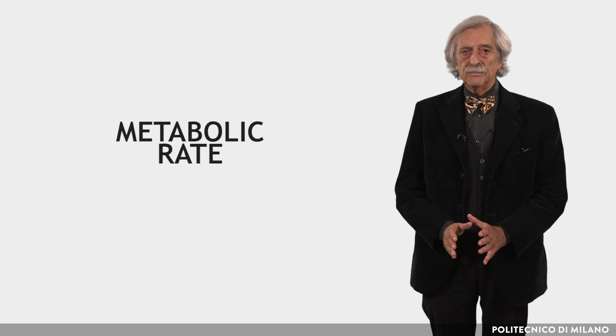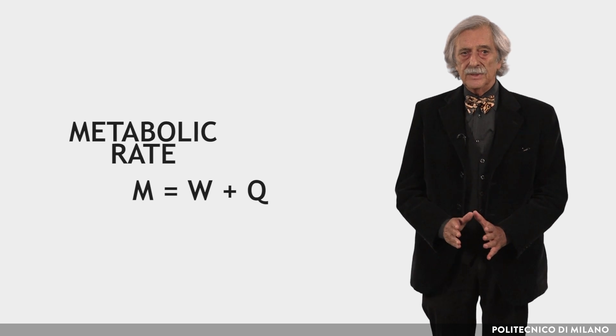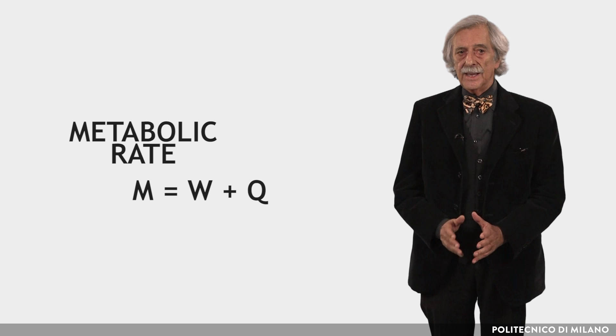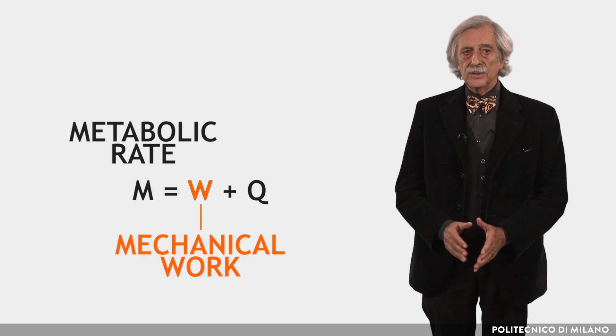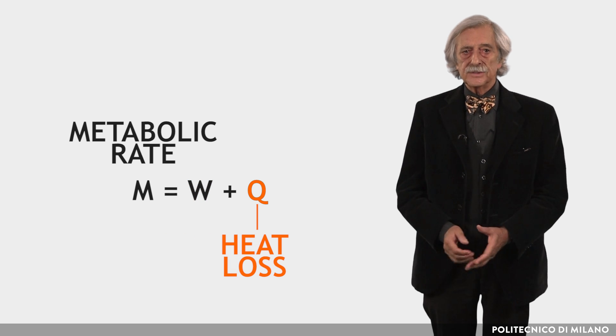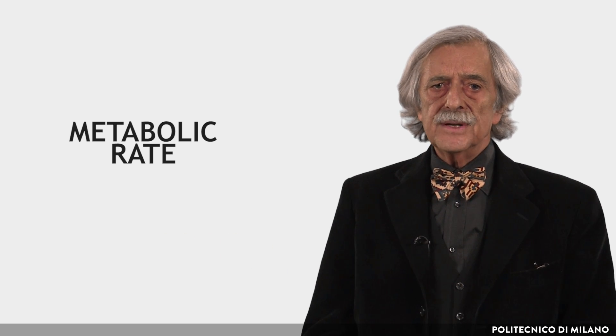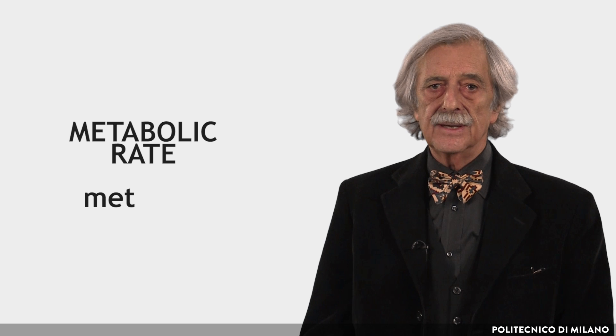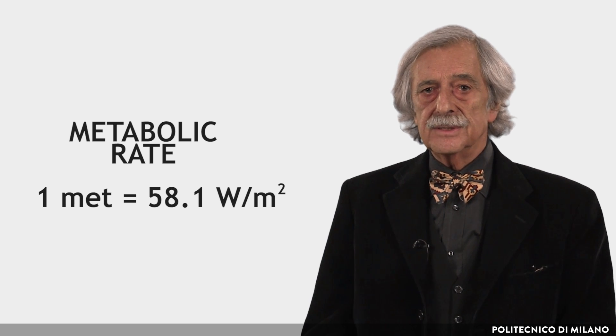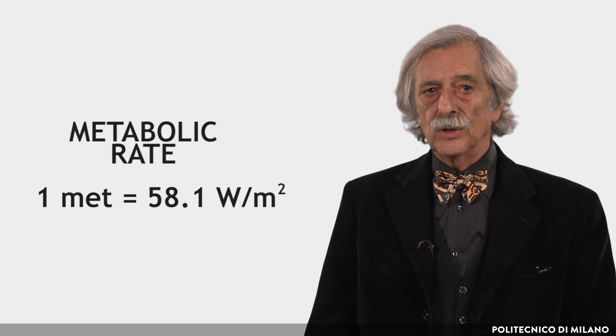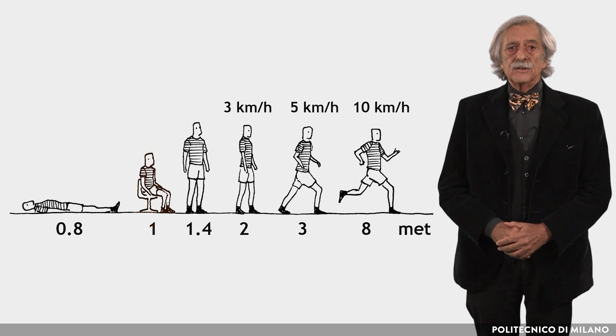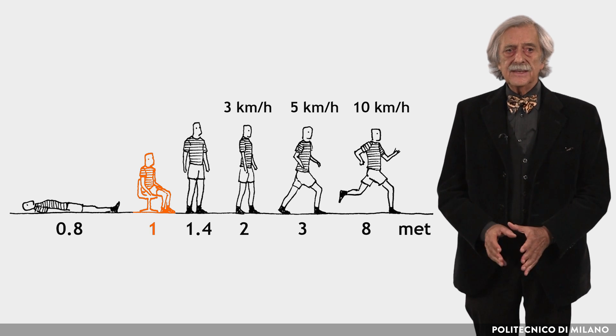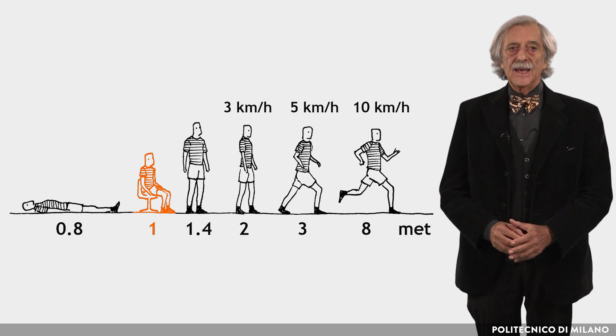The energy balance of our body can be written as M = W + Q, where M is the metabolic rate, W is the mechanical work, and Q is the heat loss. The metabolic rate is expressed in MET, or in W per square meter of body surface area. One MET is equal to 58.1 W per square meter. A seated person produces one MET.